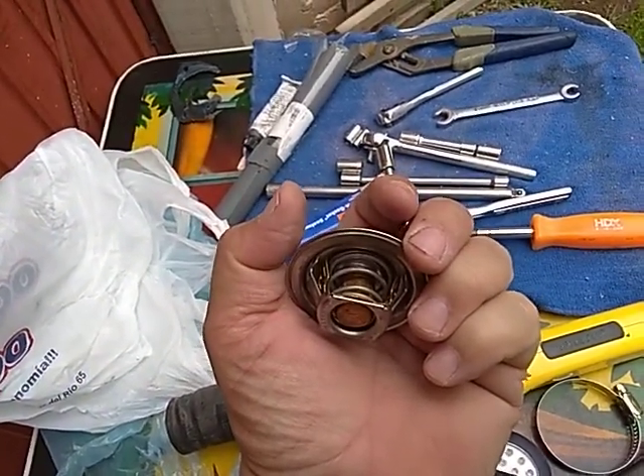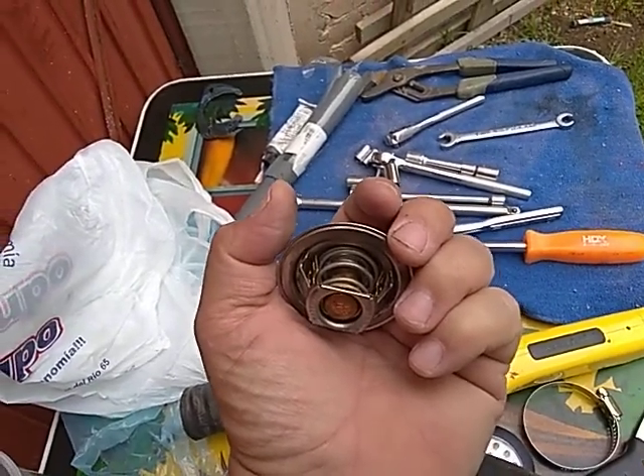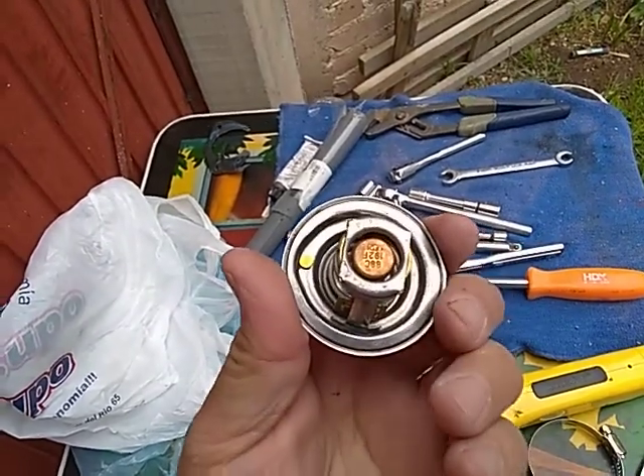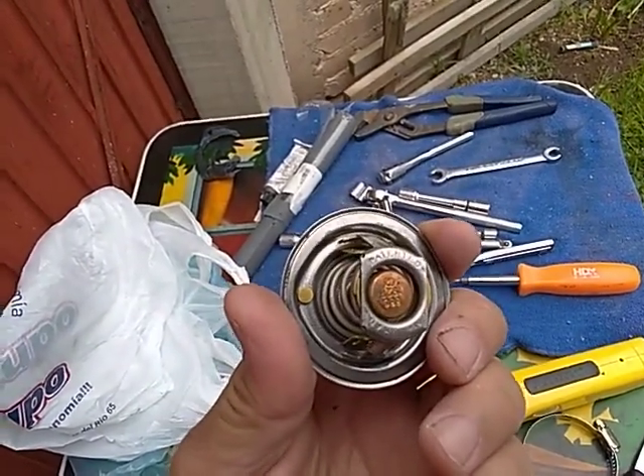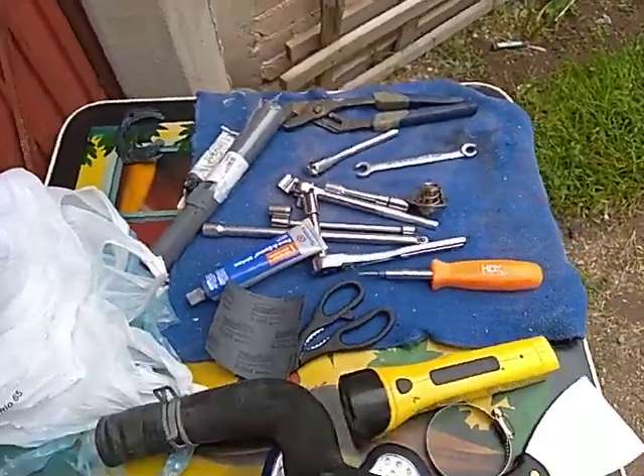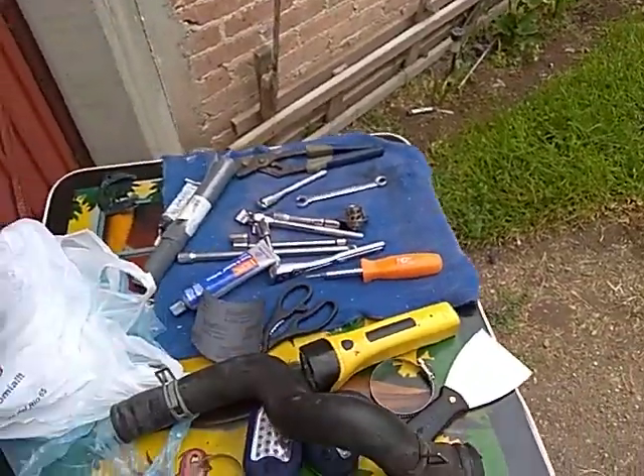It clicks open and stays open. It doesn't click closed, which I never understood. Why a thermostat was made to click closed when it malfunctions — that's the stupidest thing. You ruin a motor. Many motors have been lost because of that. So this is why I go with these.